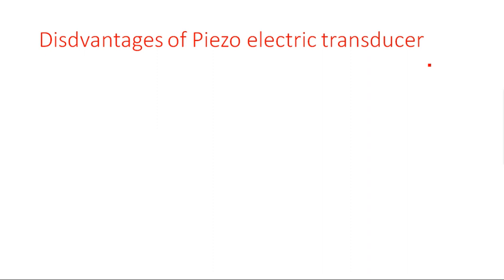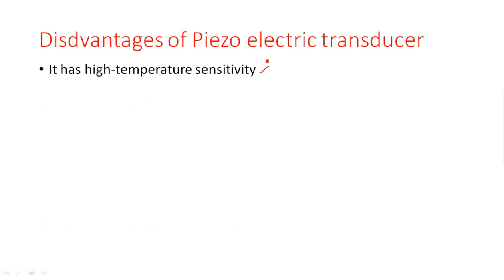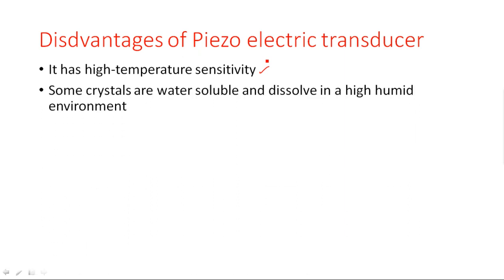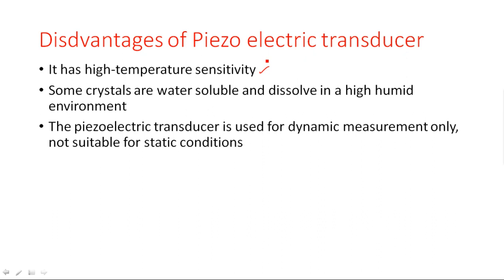The disadvantages of piezoelectric transducers include: high temperature sensitivity — when temperature increases, there is a change in output voltage. Some crystals are water soluble and dissolve in high humidity environments. Additionally, the piezoelectric transducer is used for dynamic measurement only and is not suitable for static conditions.